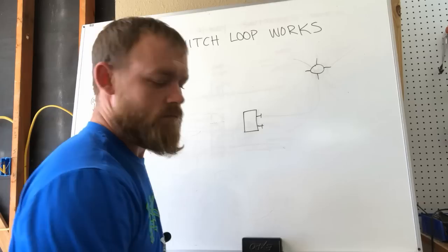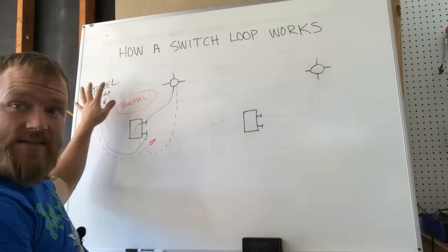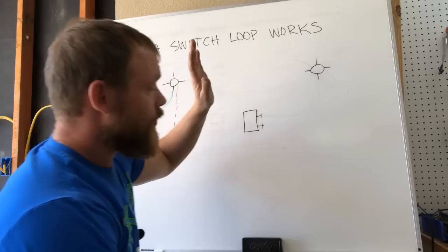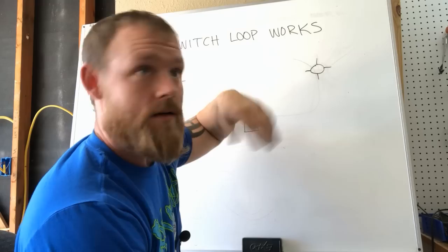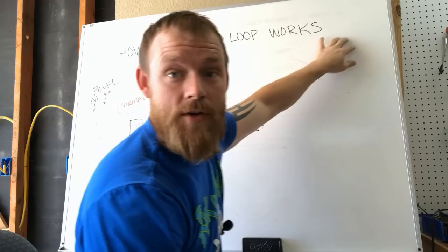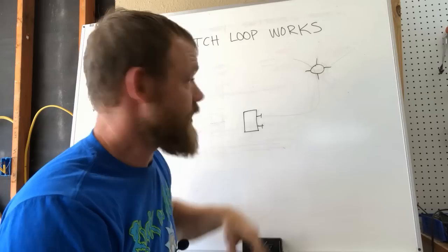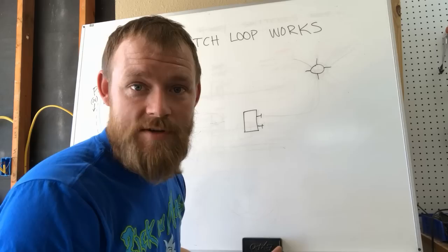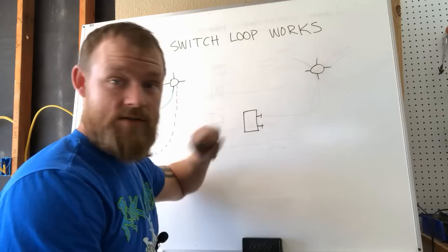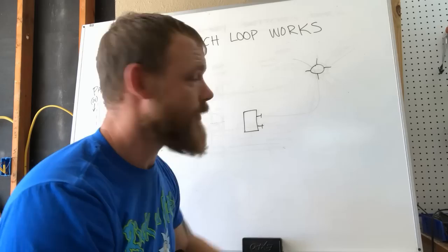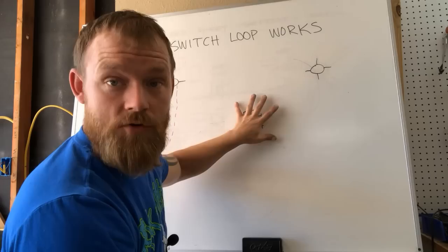All right, so the difference in a switch loop is that instead of bringing our incoming hot over to the switch first and then running our leg up and creating a loop that comes back to the panel, we're going to bring our hot into the light. And this light is going to be up in the ceiling or wherever. The whole idea is that you're sending a hot and a neutral into here and you're leaving that neutral up. You're not going to run a neutral down here because a switch doesn't need a neutral. A switch just needs a hot in and a hot out. You can think of a switch as basically one wire that goes from the panel all the way up to a light. And what you're doing is you're putting a switch in the middle of it to be able to turn that off and disconnect that wire and cut it in half, basically.